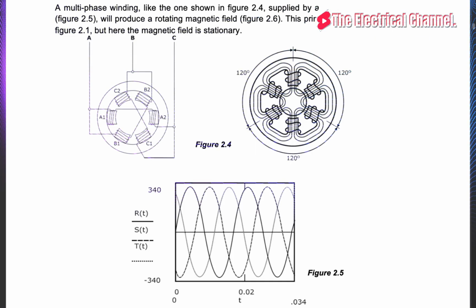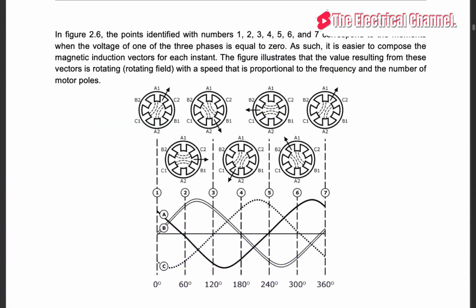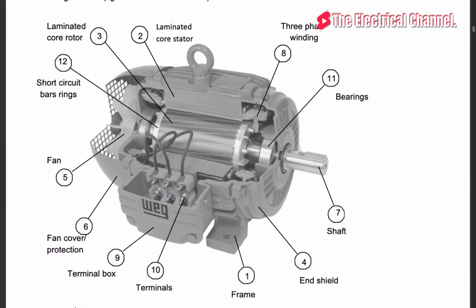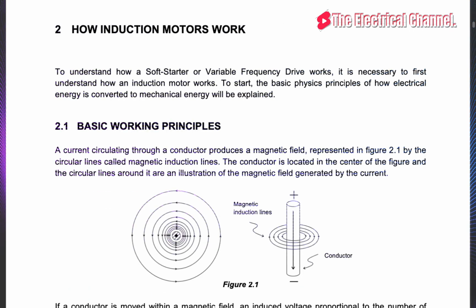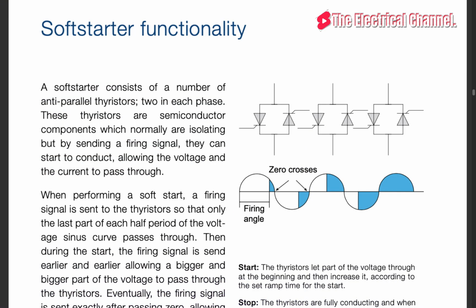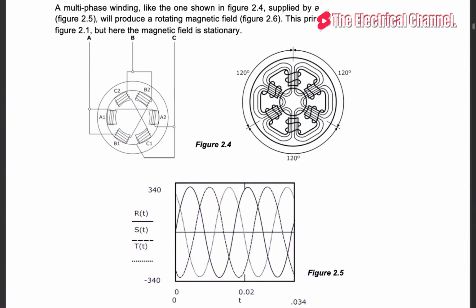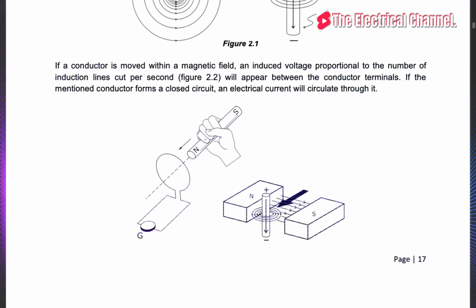When performing a soft stop, the opposite happens. At first, the full voltage is allowed to pass through the thyristors. As the stop proceeds, the firing signals are sent later and later, allowing less and less of the voltage to pass through until the end of the voltage ramp is reached. Then, no voltage is applied to the motor, and the motor stops.